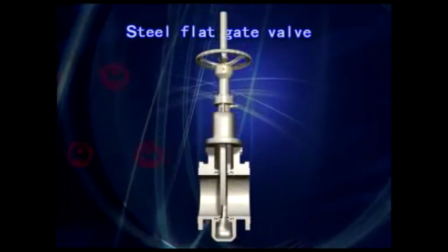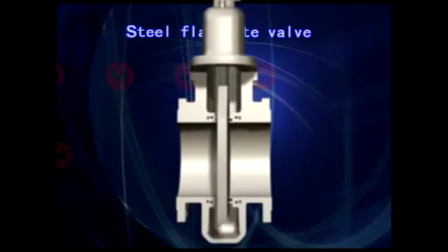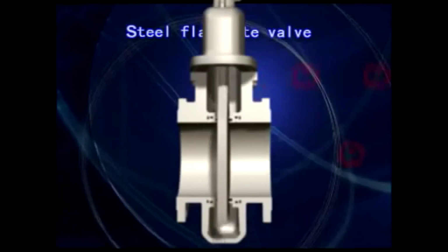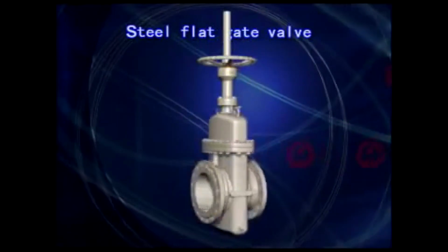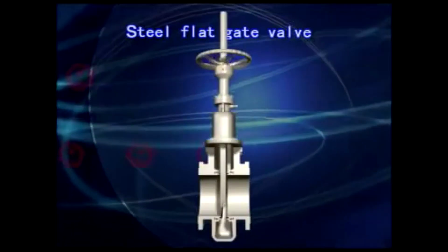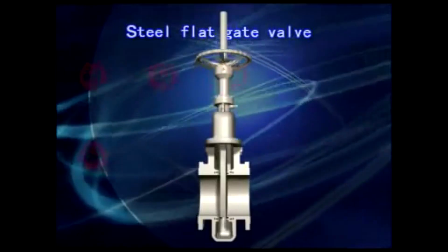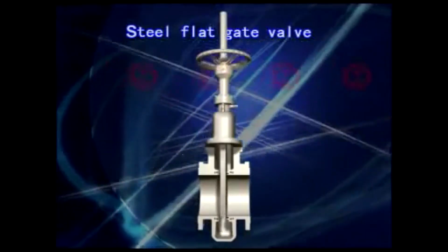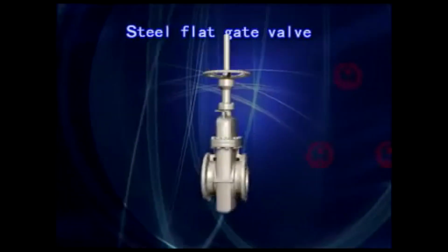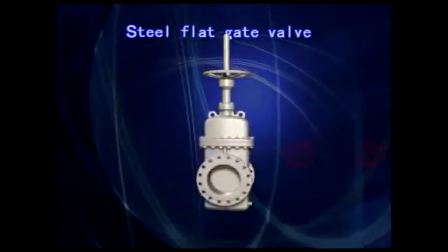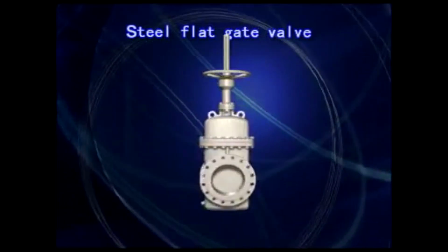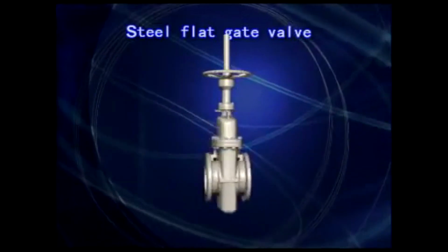3. The seat adopts PTFE embedded on the sealing surface with a double seal of PTFE to metal and metal to metal, and also the PTFE sealing surface can remove the dirt. 4. For metal-to-metal sealed valves, there's a greasing mechanism on the exterior of the valve body. Grease is filled into the seat sealing area by a greaser to achieve zero leakage of the valve. 5. The gate valve with a diversion hole always dovetails with the sealing surface, whether fully open or fully closed, so that the sealing surface is protected from direct washing by the medium, thus extending its service life.